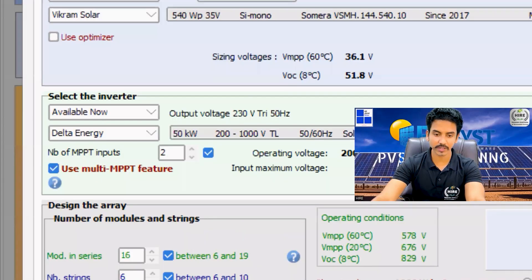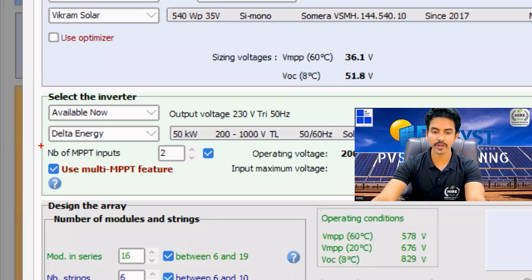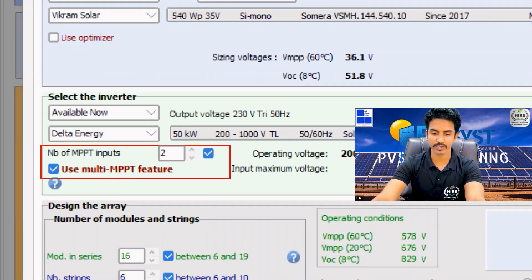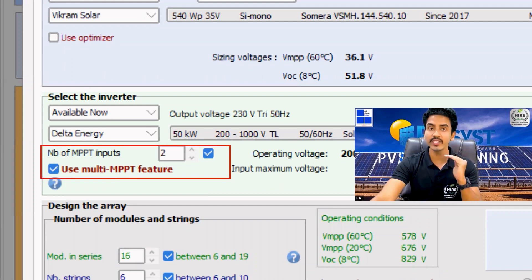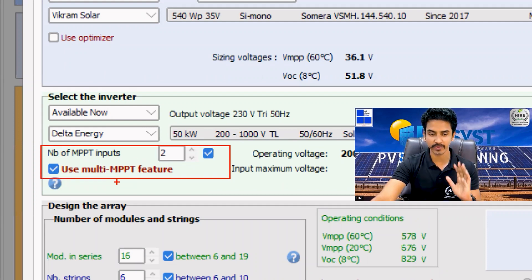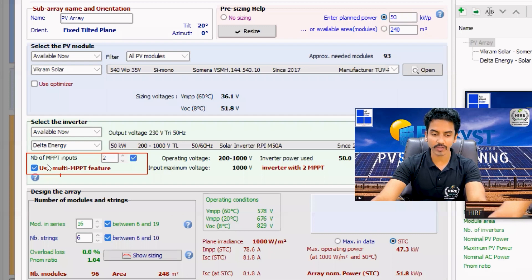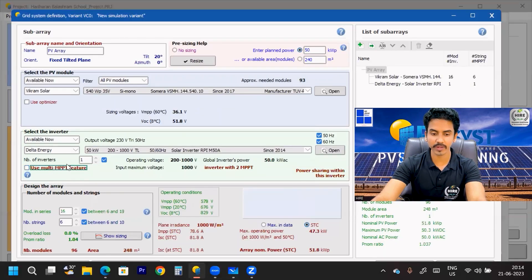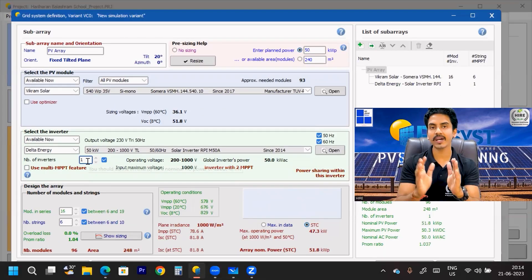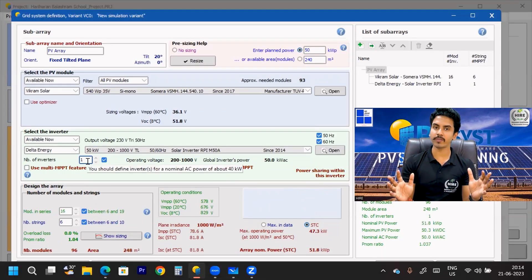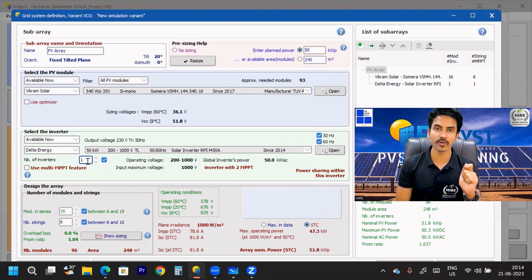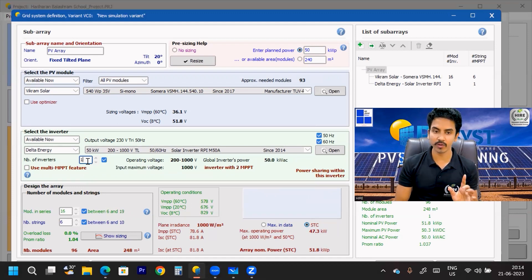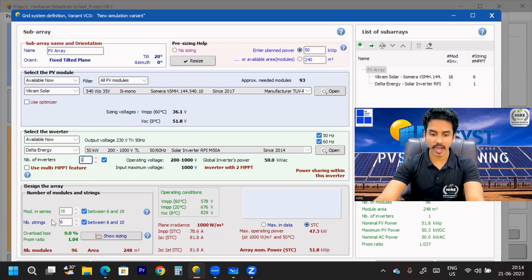Inside the MPPT option, most people get confused about what to choose — MPPT or multi-MPPT. In this case I am not going to use the multi-MPPT option. I have a 50 kilowatt plant and I want to use a single 50 kilowatt inverter, so I have used this 50 kilowatt one-inverter configuration. Now I need to consider the string configuration.